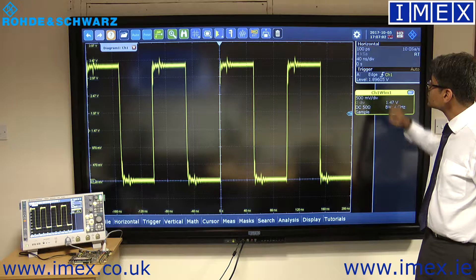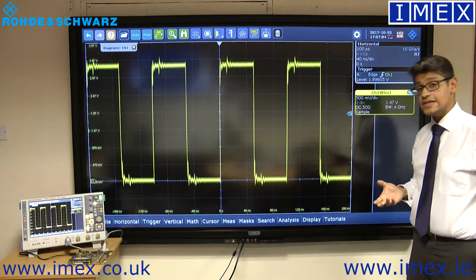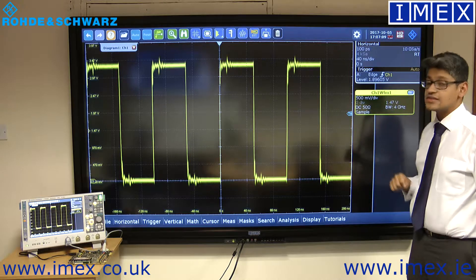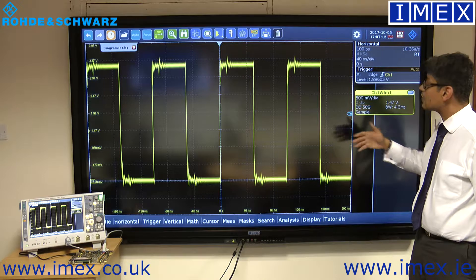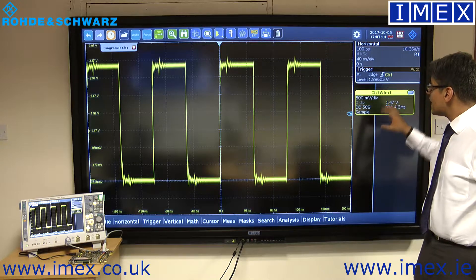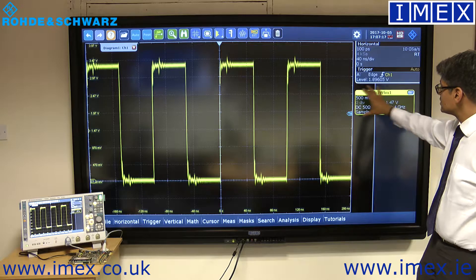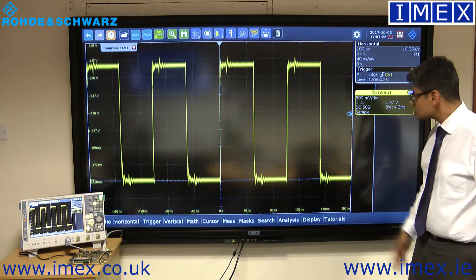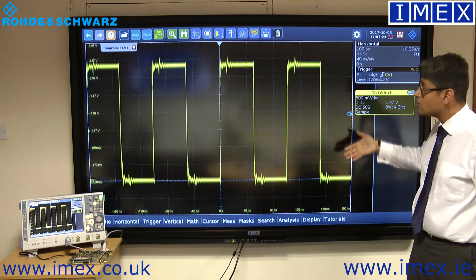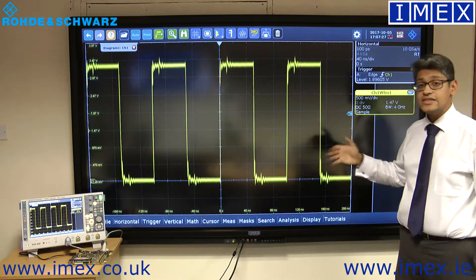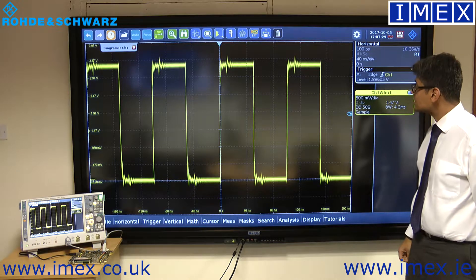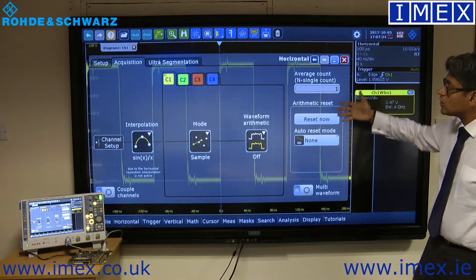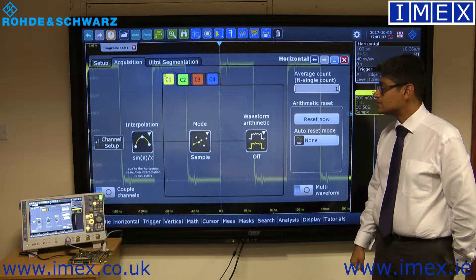So things like the horizontal settings on the top — what the ADC is sampling at, the record length, and the time scale. You've got trigger settings just down at the bottom, showing you the trigger level and trigger type. And for a particular active channel, there's a bubble here which gives you the vertical settings — such as whether it's DC or AC coupled, 50 ohms, and so on. For any of these you can just tap and go into that particular menu to set them up.